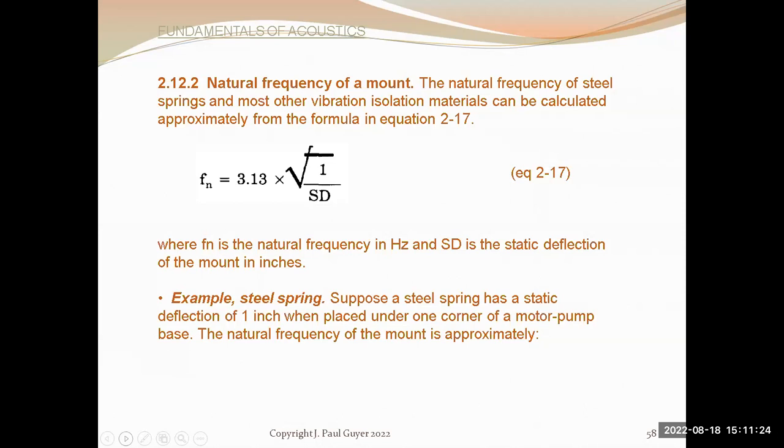These are like a little spring in a housing, and you put one on each corner of the supporting structure, and then you put the fan on top of that, and the fan, when it's running, is bouncing up and down, but the bouncing is absorbed by the spring isolators and is not transmitted to the building structural elements, except if the fan happens to be running at the natural frequency of the spring isolators.